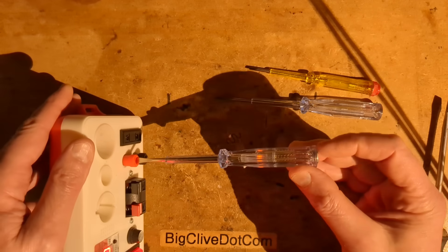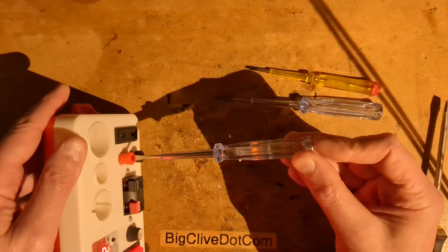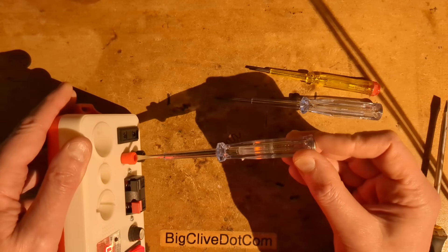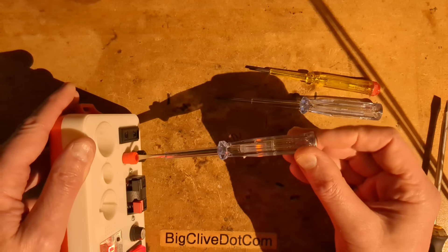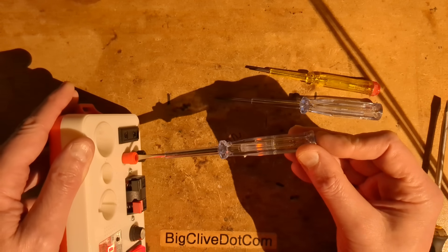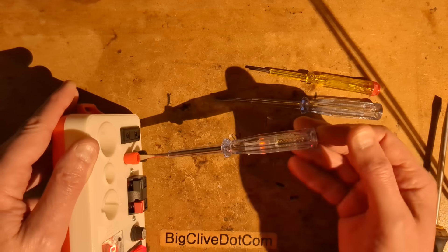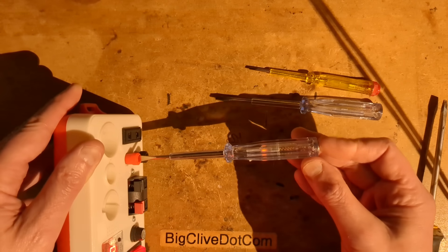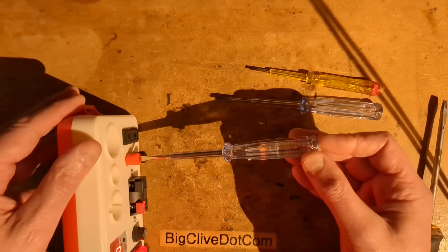Okay, this should be better. See, this is the problem. You can see it glowing. It actually is significantly brighter on camera than it is to the eye. And that is one of the main problems with the neon drivers because it's hard to get a decisive is it live or not from them because it can glow very dimly.